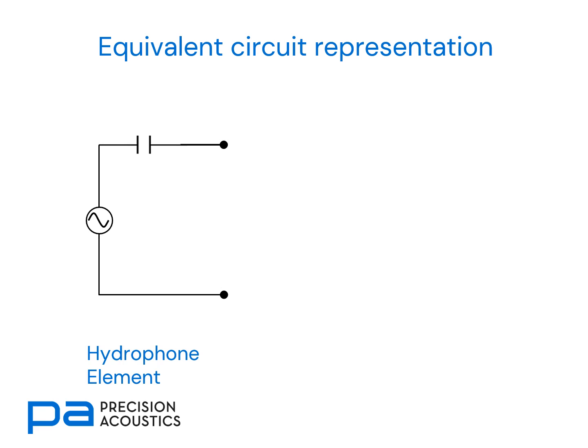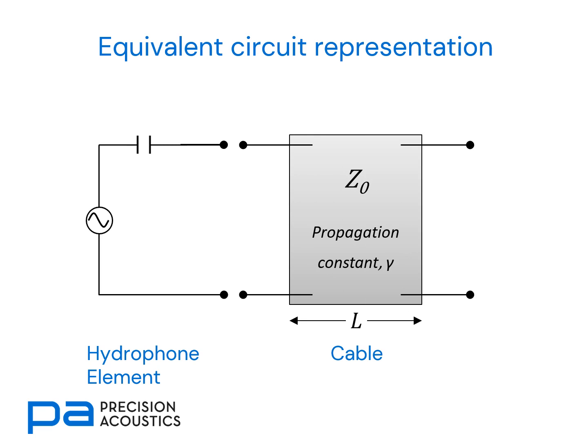Paired with the equivalent circuit representation of a simple hydrophone connected directly to a cable without a preamplifier, we have the hydrophone active element, which comprises a voltage source. In this case, we've represented the source impedance as a simple capacitor. This is usually sufficient for piezopolymer active elements. There is then connection via a cable of known length and known properties, and a load impedance — typically the 1 megaohm or 50-ohm input impedances of a data acquisition system or oscilloscope.